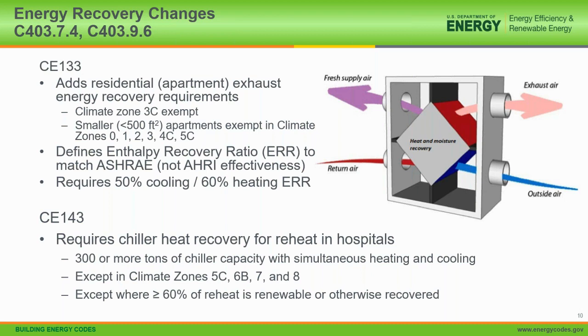Now, this is not the same as the AHRI effectiveness, which basically is independent of the balance of return or exhaust air and outside air. This requirement of enthalpy recovery ratio does need to be calculated by climate zone, and the manufacturers are getting on board to provide that information in their submittals. It does require a 50% cooling recovery and a 60% heating recovery, and that enthalpy recovery ratio covers both latent and sensible recovery, so it brings them together.